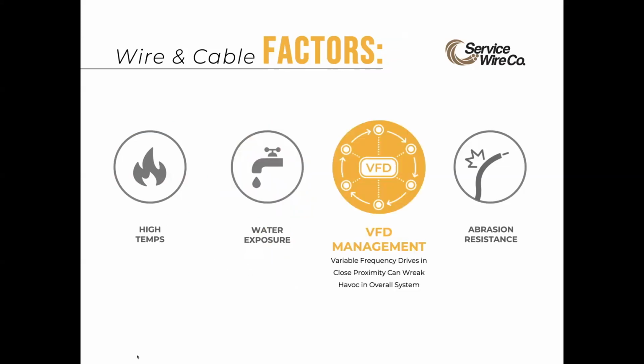Some facilities could have 15 to 20 or more low voltage variable frequency drives in one plant process alone. This can significantly vary by size and facility type. Having multiple drives so close together can really wreak havoc on your overall system if the proper cable termination methods are not implemented.